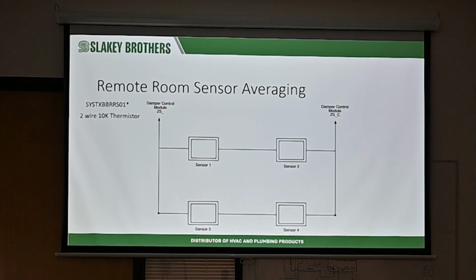And in this scenario here, any 10K ohm thermistor is how the Bryant Evolution stuff works. So if you're in a pinch and all you can do is find Honeywell for the meantime, or Aprilaire makes those, you can put it to the wall and then put a little bit of putty over it to blend it in so you can't even see the sensor in the wall. As long as it's a 10K ohm thermistor, you can use it with the Bryant Evolution stuff, or with the Bryant thermostats, period.